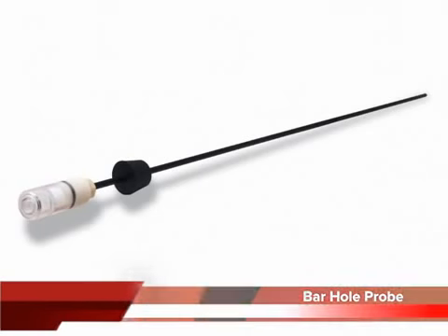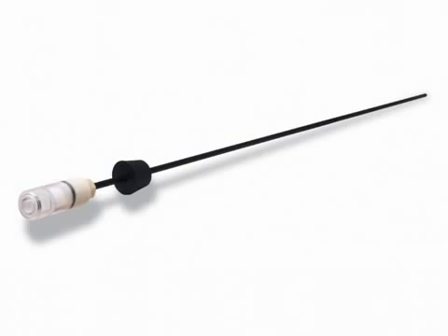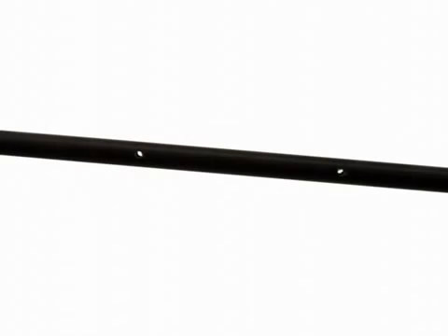An optional bar hole probe is available for the GX 2012. It is designed to be used when the GX 2012 is operated in bar hole mode to check bar holes when tracking down underground gas pipe leaks. The bar hole probe has the same handle as the standard probe, but has a 30-inch fiberglass tube instead of the standard tube. 4 holes are drilled through the 30-inch tube's wall near the end, and the end is plugged so that debris from the bar hole cannot be drawn into the tube. The sample is drawn through the drilled holes in the tube wall.